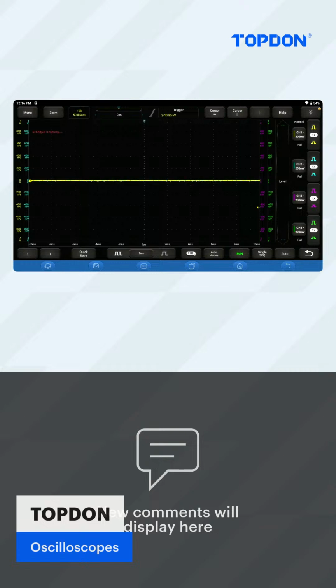Again, the self-adjust takes a little bit of time, probably maybe a minute and a half, something like that. But we want to make sure we do this typically on a once a day basis when we're going to use the scope. It doesn't take very long. You can see we've got the little notice in the top left corner, self-adjust is running. And once it's done, that little note is going to disappear from the screen.